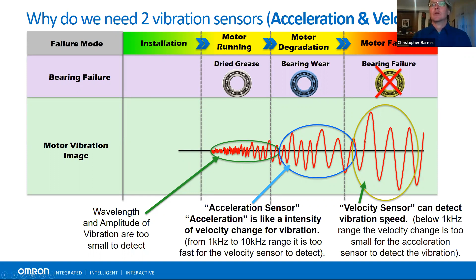So what we're talking about here is a technology that combines acceleration, velocity, and temperature into a sensor that you can mount directly on a motor. But you can also mount it onto a bearing. It was designed specifically for motors because that's the most common failure point. It will also pick up bearings that are along the shaft. There are some fan motors we've put it on where this sensor picks up a bearing failure that wasn't on the motor, but on a fan that was directly coupled to it. It gives you a couple of ideas. You can tap it in or you can attach it with a magnet, and again, back to where you're going to use it.